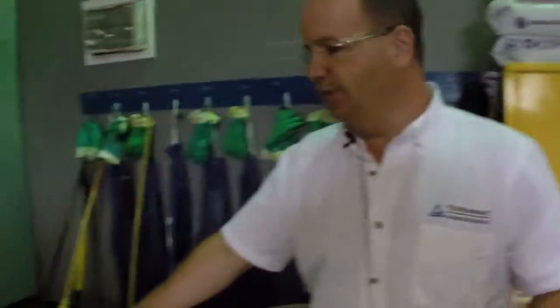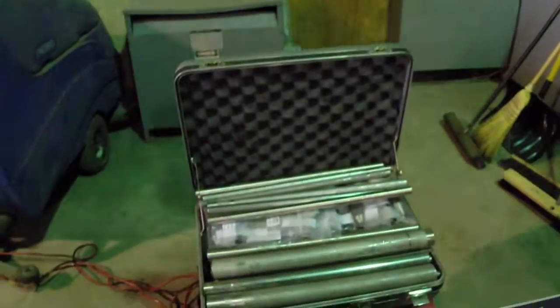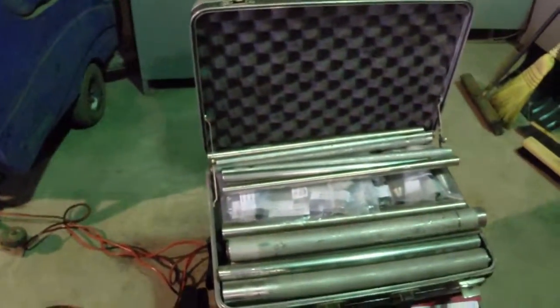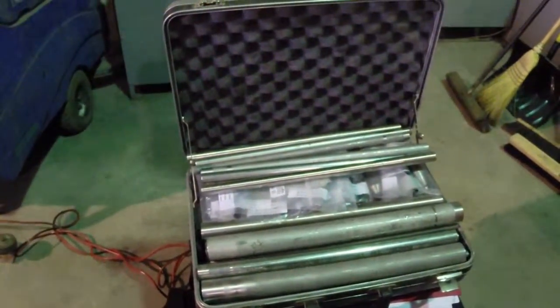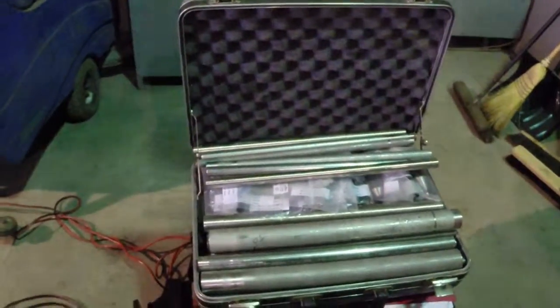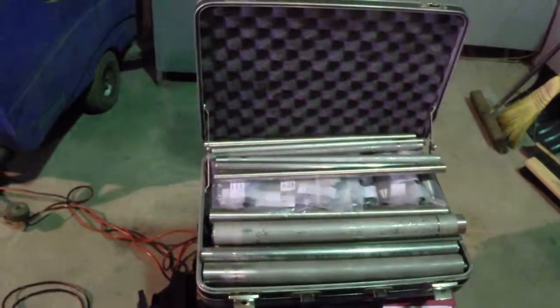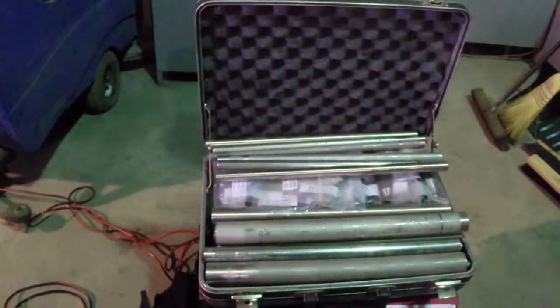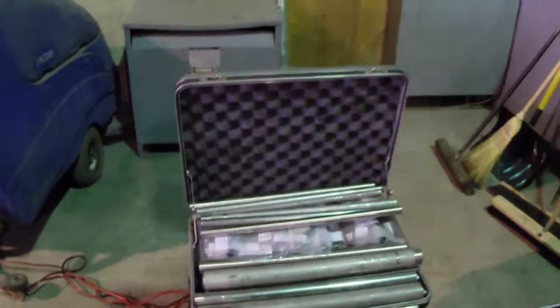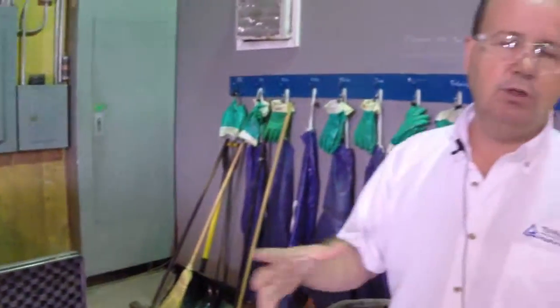Field service anywhere. This is all the equipment that's needed. We have multiple tubes that we've done, calibration standards. Each tube material, diameter, and wall thickness needs a calibration standard. So to set up, you have to have all of this equipment, because multiple exchangers have multiple different tubes and materials due to the service conditions they're going to be in.